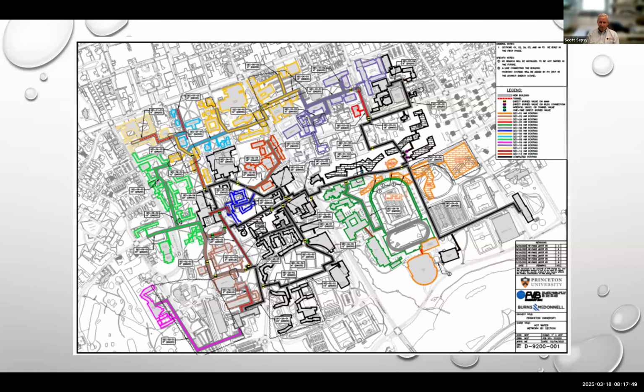This is a map of the campus showing the new hot water piping network. The Tiger plant on the far right and the cogen plant over here on the bottom left are now tied together by the black lines. The black lines are already installed, and that was the first thing we had to do, was connect these plants so they could back each other up. And we've built out the engineering quad and built out into the central campus for dormitories. And the colored buildings and lines, piping lines, are yet to be built.